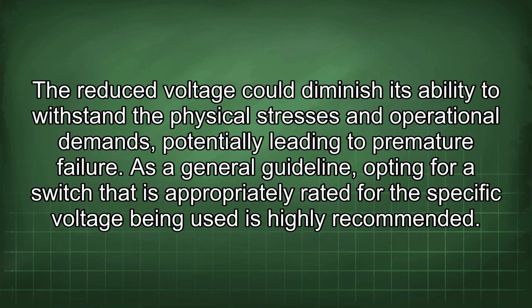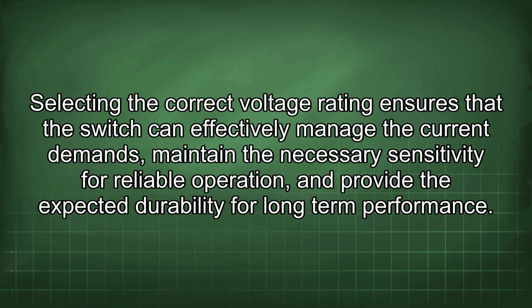The reduced voltage could diminish its ability to withstand the physical stresses and operational demands, potentially leading to premature failure. As a general guideline, opting for a switch that is appropriately rated for the specific voltage being used is highly recommended. Selecting the correct voltage rating ensures that the switch can effectively manage the current demands, maintain the necessary sensitivity for reliable operation, and provide the expected durability for long-term performance.